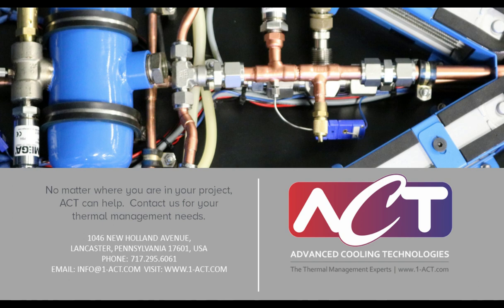Thank you. What kinds of working fluids are used in a pumped two-phase cooling solution? Most commonly, we use dielectric refrigerants. They offer good benefits in terms of their latent heat, and they typically have the right boiling point and pressures for most systems. They also don't freeze under normal transit conditions, and they're dielectric, which is a benefit to a lot of applications. But they aren't the only solutions. We've done some water two-phase cooling solutions, as well as some alcohols. So it really depends on the particular application as to which working fluid we use.